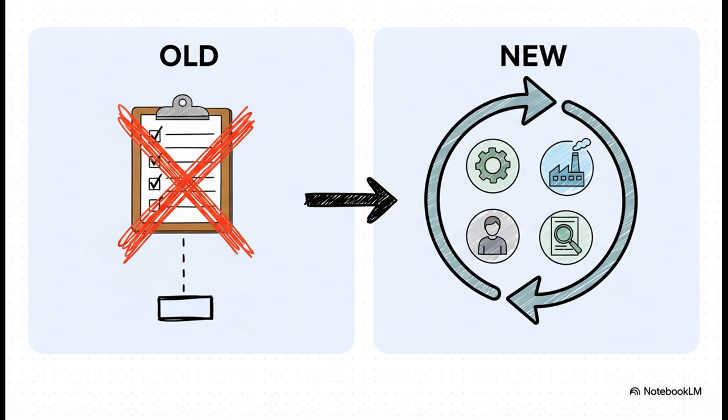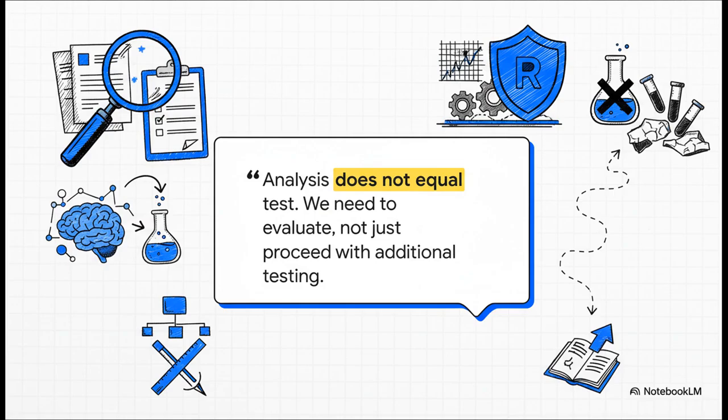Well, the new standard basically throws that whole recipe out. Instead, it demands an integrated risk management process, one that's deeply woven into the principles of ISO 14971. Evaluation isn't the last thing you do. It's something you do continuously throughout the device's entire life cycle. The whole spirit of this new standard is captured perfectly right here. Analysis does not equal test. It's a huge push for more scientific thinking, more justification before you even dream about running a test. The goal is to truly evaluate the risk using all the data you have, all the scientific principles you know, not just to blindly run down a list of tests because a table told you to.